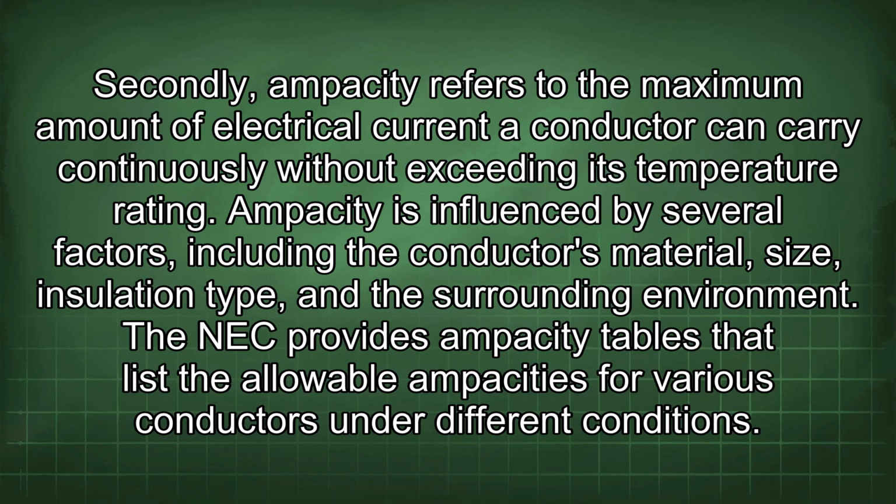Secondly, ampacity refers to the maximum amount of electrical current a conductor can carry continuously without exceeding its temperature rating. Ampacity is influenced by several factors, including the conductor's material, size, insulation type, and the surrounding environment. The NEC provides ampacity tables that list the allowable ampacities for various conductors under different conditions.